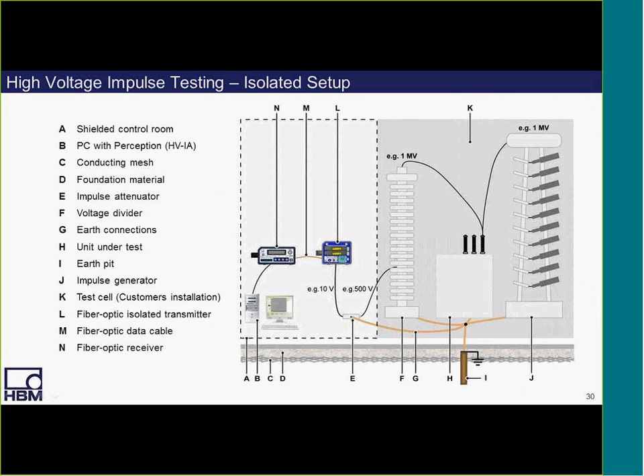60060-1 and -2. So here on this page, we see a test bench set up going from, let's say, right to left, starting from the middle of the diagram at the existing lab's voltage divider we call F. We then connect to item E, which is the high voltage 50 to 1 impulse attenuator, which is capable of accepting up to 2,000 volts RMS. That's the device we showed you in the previous slide.